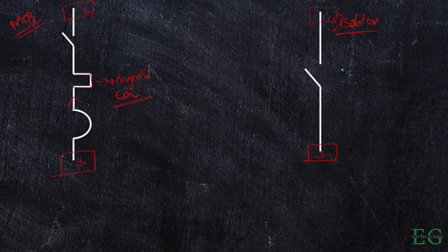Whereas the curved or bent line represents your bimetallic strip. These parts bend slowly when the current stays higher than normal for some time, giving you overload protection. Whenever any of these conditions occur, the breaker gets opened and your load is saved from the source automatically.